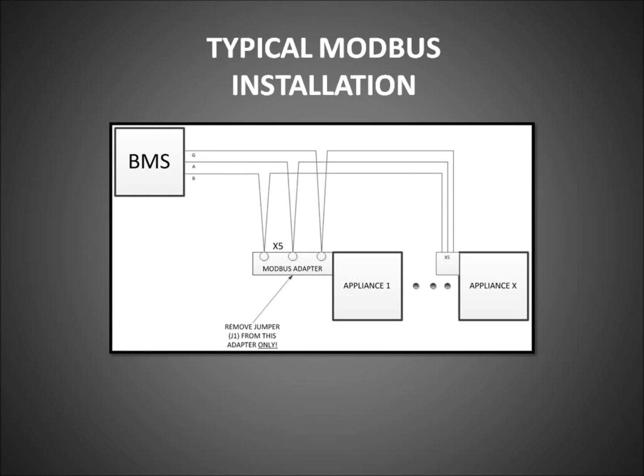This just gives you a typical ModBus installation, and later on in the PowerPoint, we'll show you 3 different ways you can wire up multiple boilers to a BMS system. There are different ways to connect the ModBus adapter to give you more information on each boiler: by having ModBus adapters on each individual boiler, or you can just have a ModBus adapter on the master and see limited information on the connected followers.